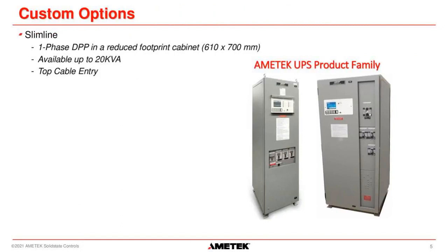One of the best-selling custom options that we do is the Slimline UPS. Obviously, if you have space requirements and you need to fit a UPS into a small area, we can do a single-phase DPP in a reduced footprint cabinet. So it's 610 by 700 millimeters, up to 20 kVA with top cable entry. You can see on the picture there on the left is our Slimline DPP, and on the right is our normal size DPP. So it really does help if you're trying to fit a UPS into a tight space.